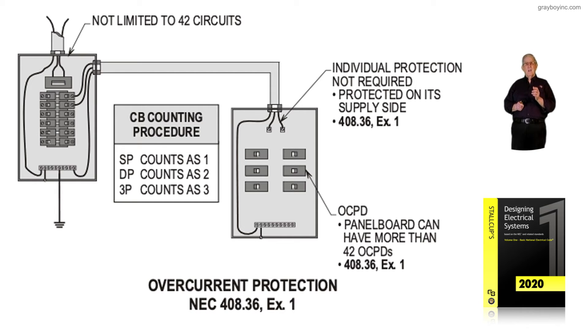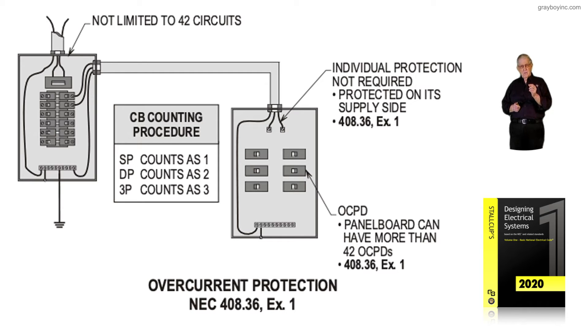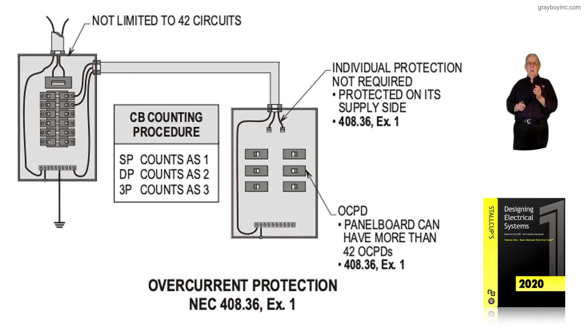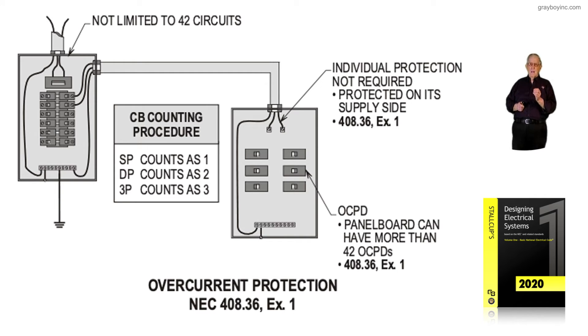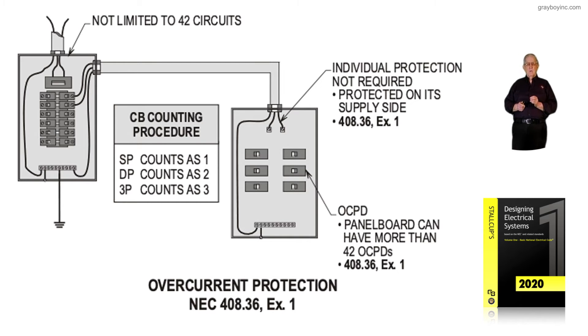Individual protection is not required on the panel to your right because the main in the service equipment protects the conductors and protects the bus bar in the panel. Notice the panel board can have more than 42 circuits if we're applying Exception 1 to 408.36.